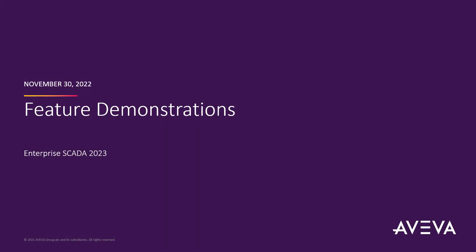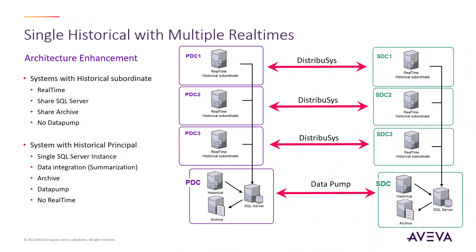Let's take a look at some of the new features in Enterprise SCADA 2023. In very large systems, it has become common to horizontally scale the telemetry across multiple real-times. Before now, that would mean that each real-time pair would be accompanied by a historical pair. At the extreme, with three horizontally scaled real-time systems and replicas at the backup control center, this would total six SQL clusters, representing a significant additional cost. Enterprise SCADA 2023 introduces single historian with multiple real-times, which is a significant new deployment topology.